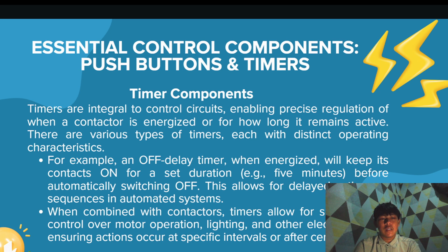Next, timer components. Timers are integral to control circuits, enabling precise regulation of when a contactor is energized or for how long it remains active. There are various types of timers, each with distinct operating characteristics. For example, an off-delay timer, when energized, will keep its contact on for a set duration before automatically switching off. This allows for delayed action or sequencing in automated systems.